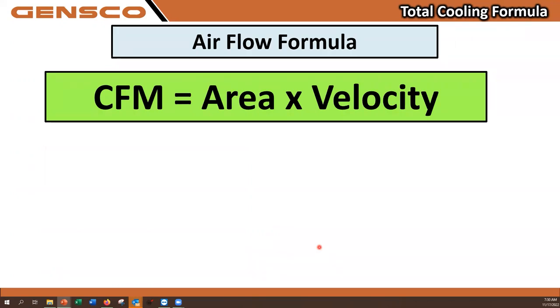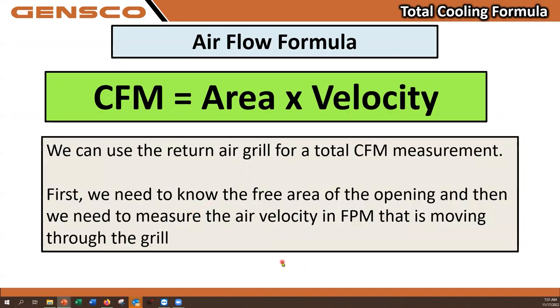This is another formula. This is a simple airflow formula. The CFM that any unit is passing through any point in this unit will be the area of that point times the velocity of the air in feet per minute that's going through that opening. And in our case, and what I'm going to do on an actual job site visit is use the return air grill. If I've got two, then I'm going to be doing two of these measurements. But the CFM will equal the area of the opening times the velocity of the air going through that opening. If you want to take a picture of that formula.